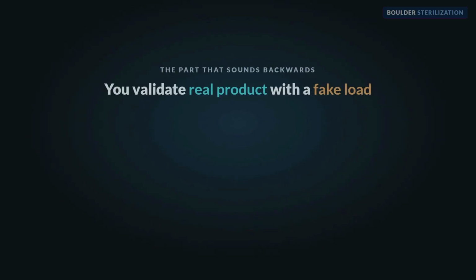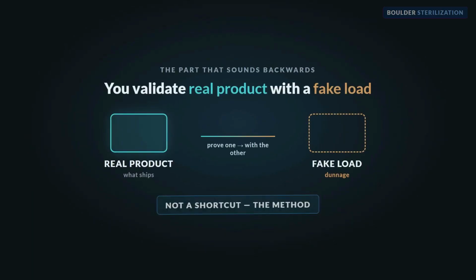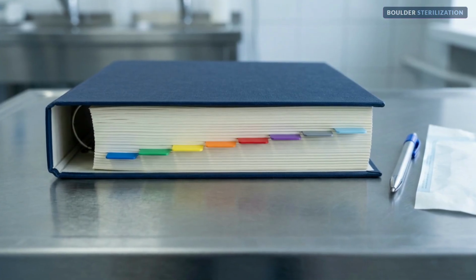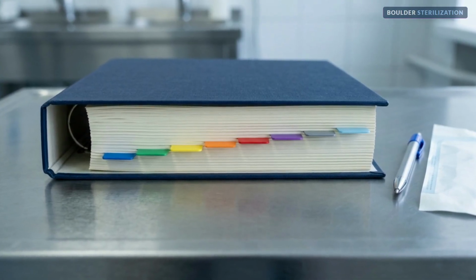validation. Instead of filling the chamber with your real product to run the tests, we take a few and fill the rest of the space with fake products called Dunnage: rejected parts, bare circuit boards, syringes filled with water. It sounds like a shortcut. It's the opposite. It's a rigorous, fully documented stand-in. And when it's justified properly, it's an approach the FDA accepts.